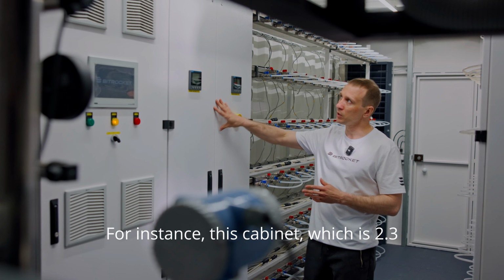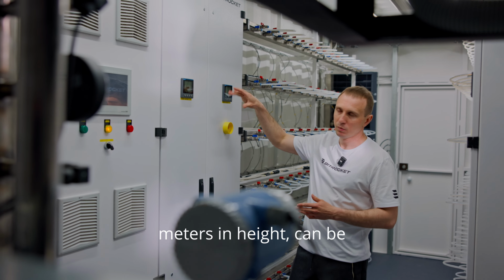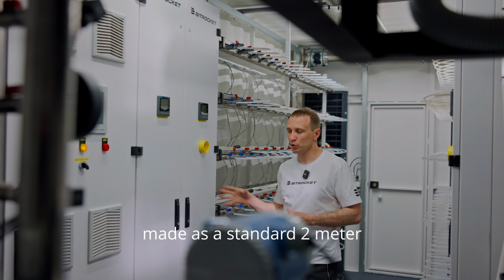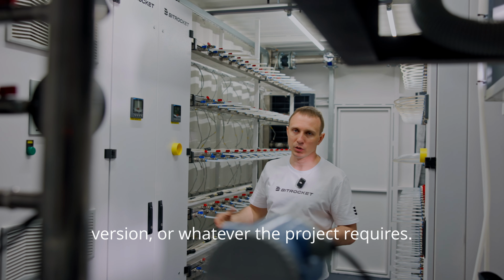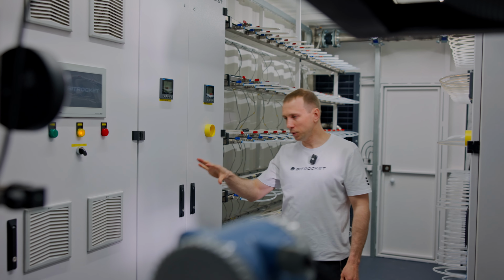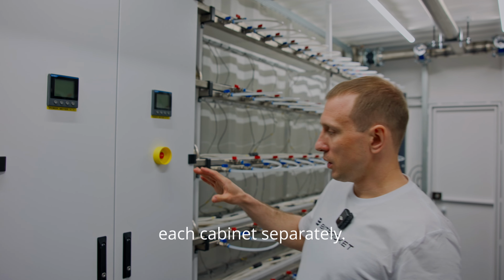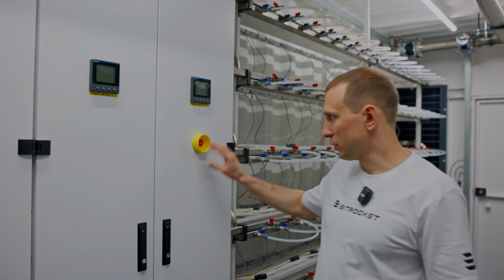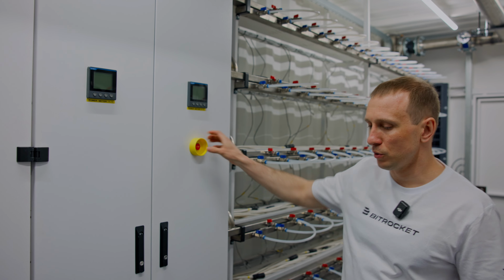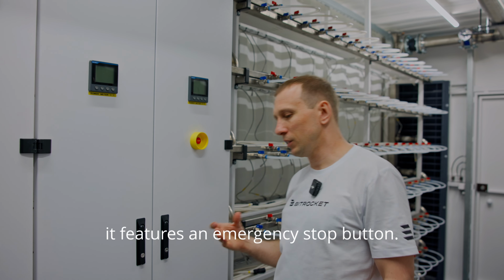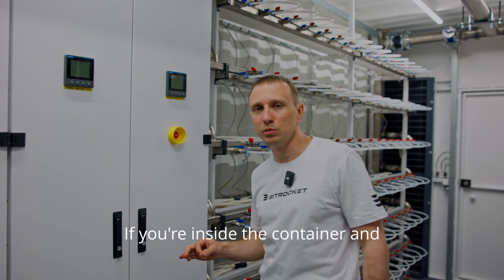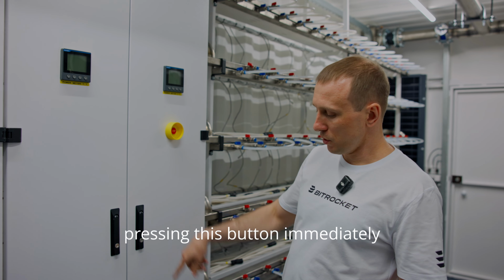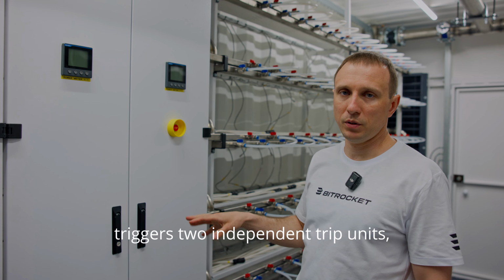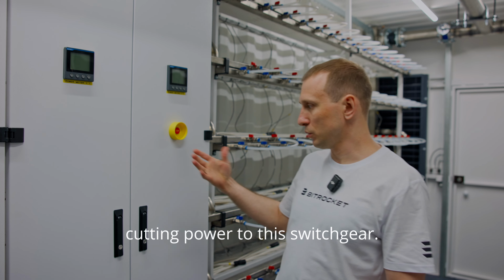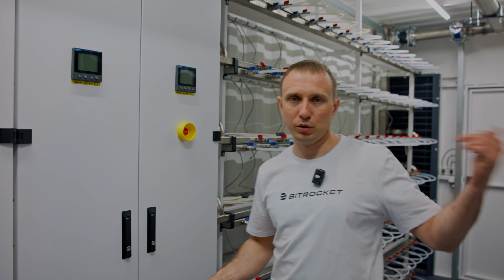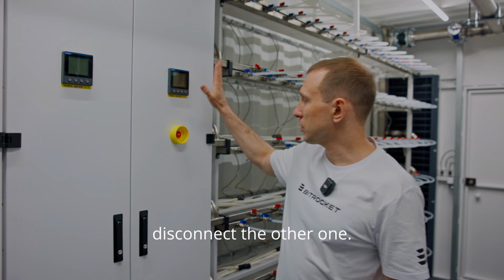For instance, this cabinet, which is 2.3 meters in height, can be made as a standard 2-meter version, or whatever the project requires. Now, let's go over each cabinet separately. First, the switchgear cabinet. It features an emergency stop button. If you're inside the container and there's an emergency, pressing this button immediately triggers 2 independent trip units, cutting power to this switchgear. And you can also disconnect the other one.